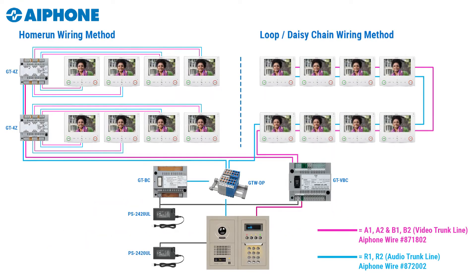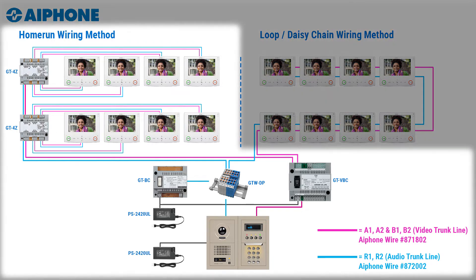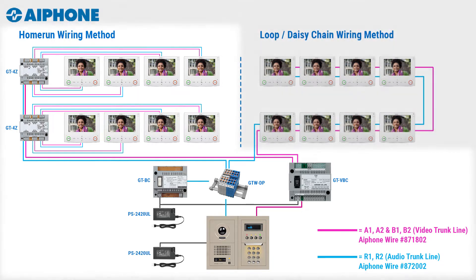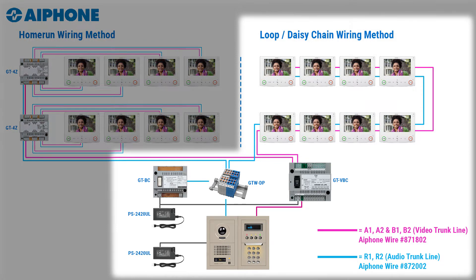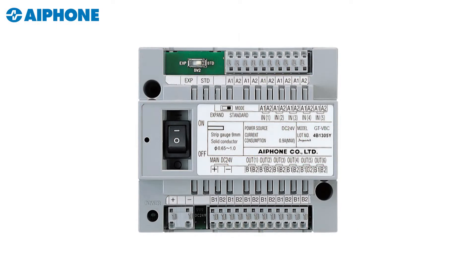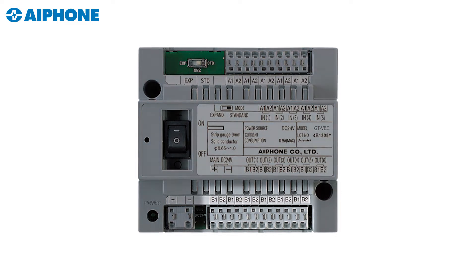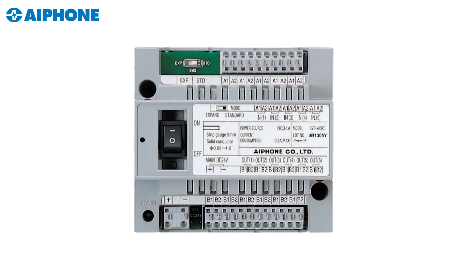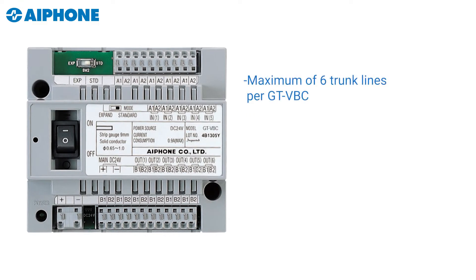There are two primary ways to wire the standard GT system. On the left hand side you'll see what we call the home run method, and on the right hand side you'll see what's called the loop method. When using either method you're limited to six trunk lines on the output of the GT VBC, and each trunk line is limited to a maximum of 25 apartments.